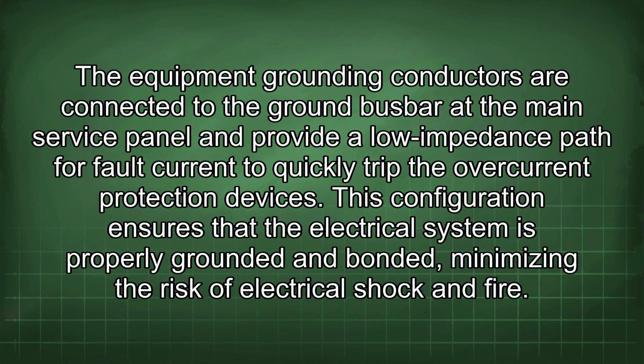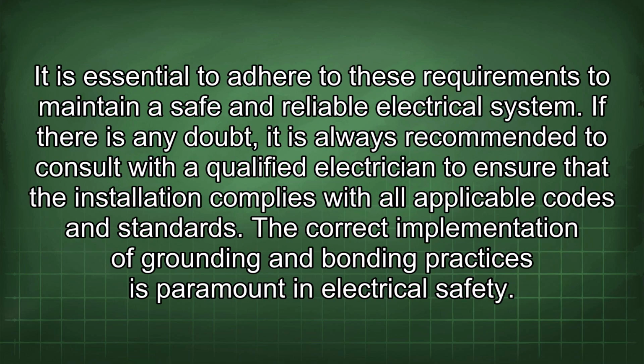The equipment grounding conductors are connected to the ground busbar at the main service panel and provide a low impedance path for fault current to quickly trip the overcurrent protection devices. This configuration ensures that the electrical system is properly grounded and bonded, minimizing the risk of electrical shock and fire. It is essential to adhere to these requirements to maintain a safe and reliable electrical system.